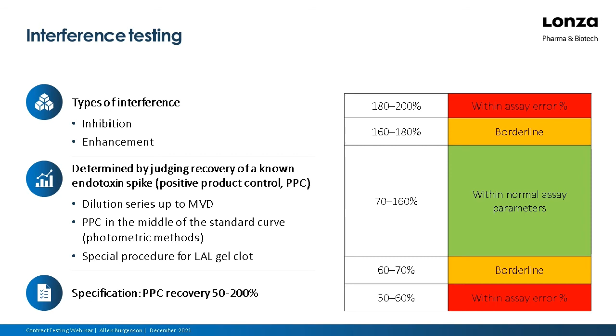Now, although you're allowed 50 to 200%, it's really not recommended to accept any values at those extremes because of the variability of the assay. So the closer you get to the extremes, the higher the probability of you having an assay that passes a product that potentially could have failed. So you're really looking at the green areas between 70 and 160%. That's ideal. With borderline, you can have between 160 and 180%, or between 60 and 70%. And only in rare cases where you really can't get an acceptable spike recovery should you accept 180 to 200 or 50 to 60%.